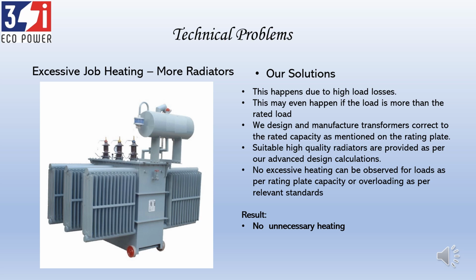That's the first step. Second, positioning: calculating the radiators by calculating the thermal head of the transformer and the position of the radiators. We do these advanced calculations based on our experience and our case studies. We developed a good calculation system for the radiators. We don't depend on the dissipation of the radiators as per our suppliers' catalogs or anything. We have our own data, and based on that we place the radiators.